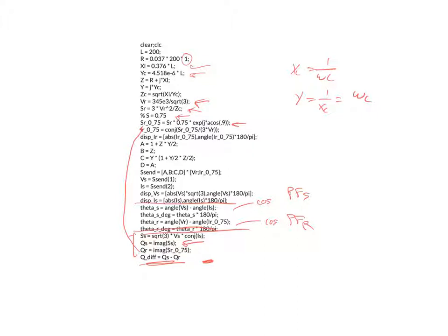If the power demanded from the load is less than the SIL, the line should be supplying VARs because the current through the line is below that break-even point when reactive power support is provided by the capacitance to ground. So the line should be supplying its own VARs, which means this number should be negative because there is less Q put in than taken out.